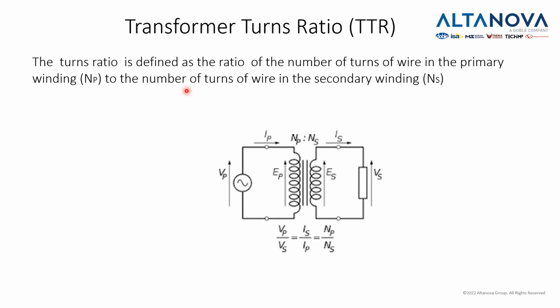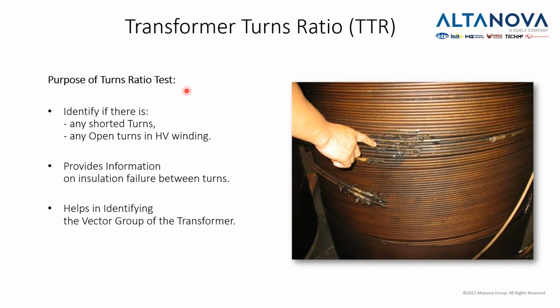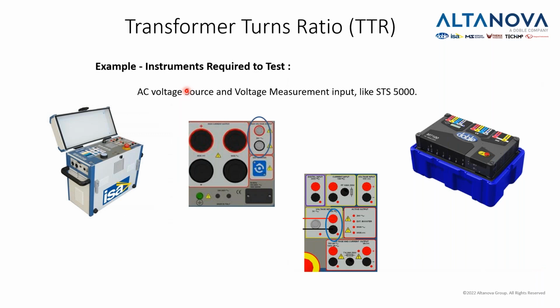Transformer turn ratio is defined as the ratio of the number of turns of wire in the primary winding to the number of turns of wire in the secondary winding. We can see here that this test can identify shorted turns or open turns, and it provides us information if there is some insulation failure between turns, and it also helps us to understand the vector group of the transformer.